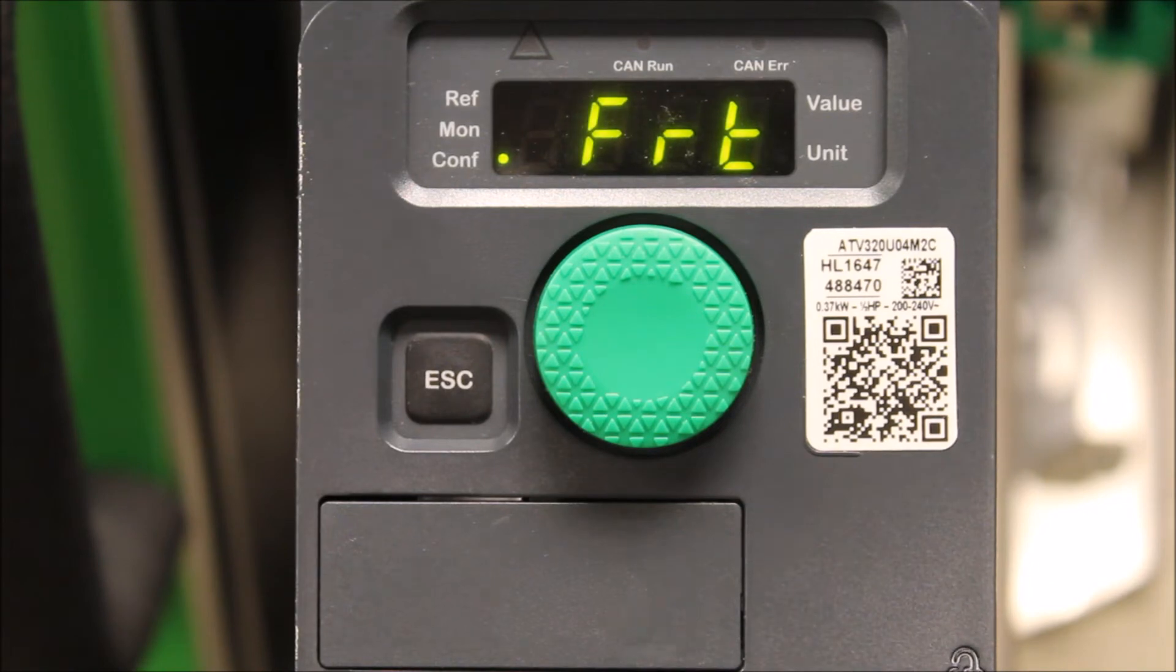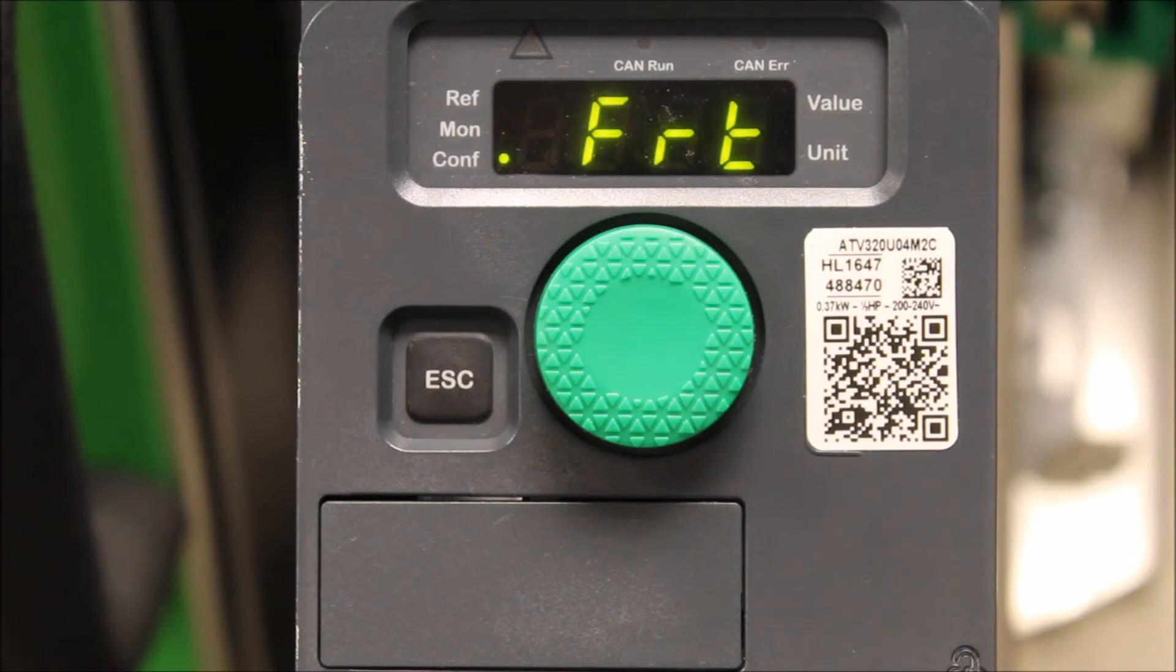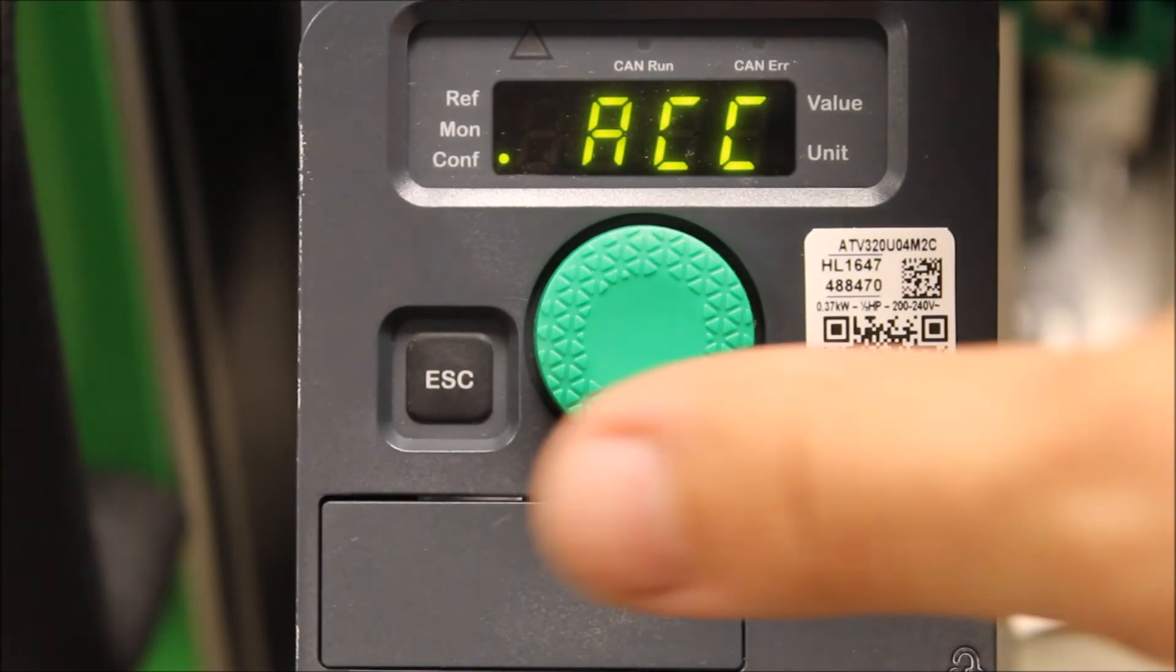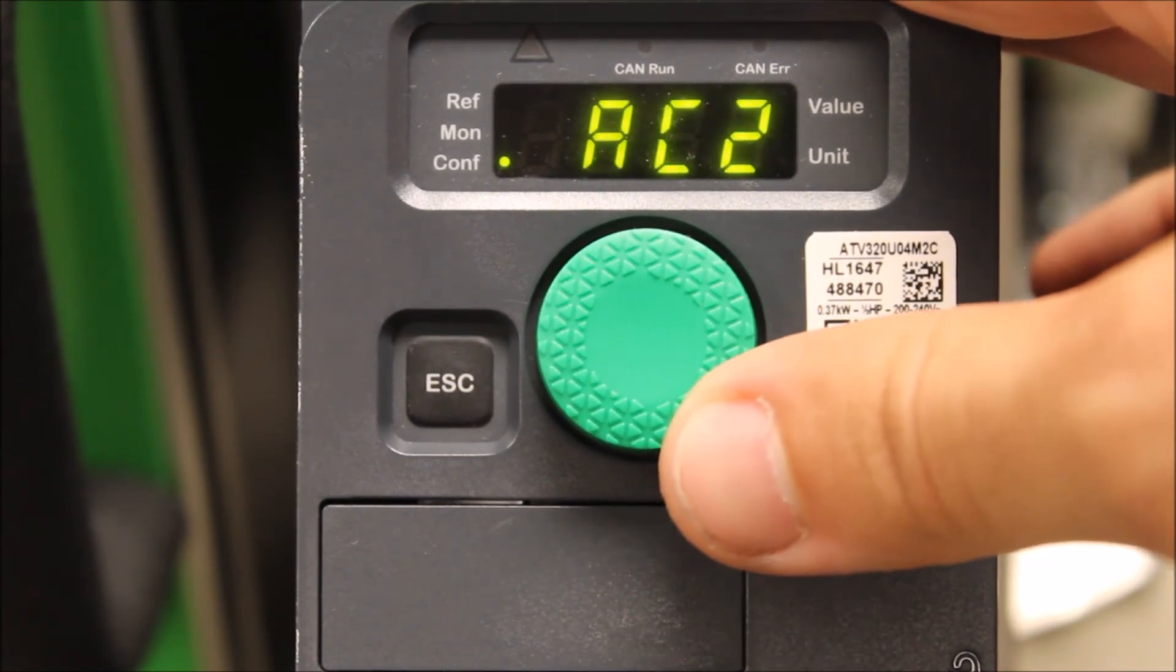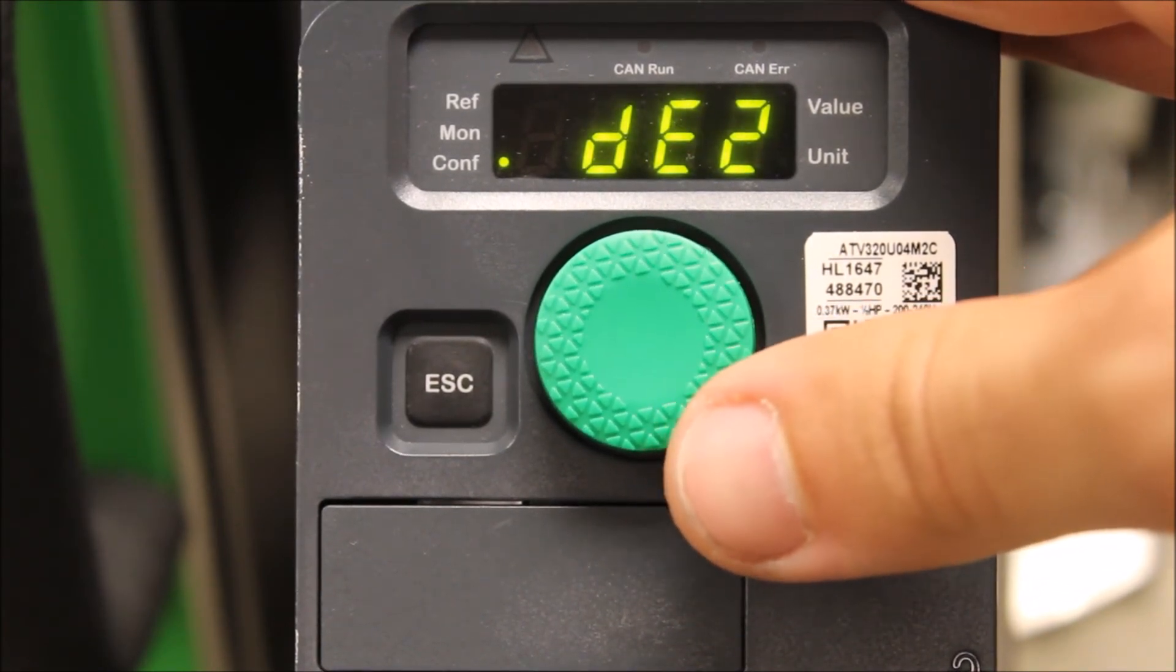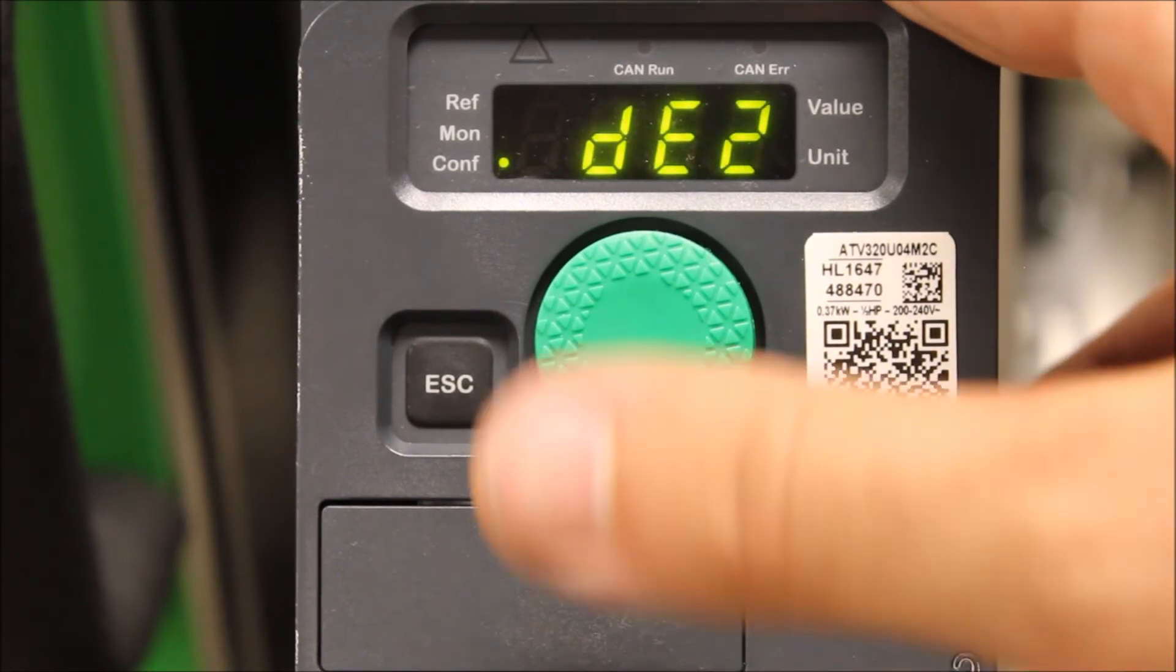it's going to follow your first acceleration and deceleration times as you programmed under Simple Start. But after 30 Hertz, it's going to follow the ACC2 and DEC2 - number 2 right here - AC2 and DE2, and these are in seconds.